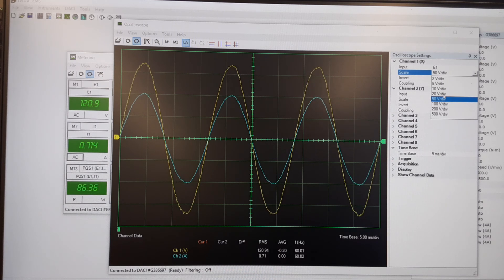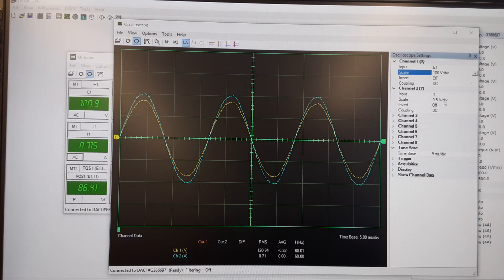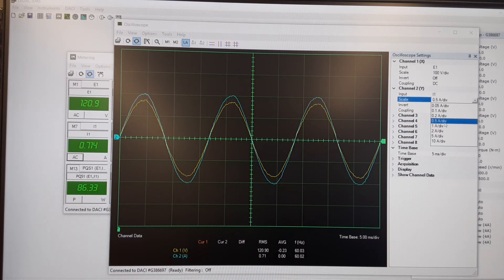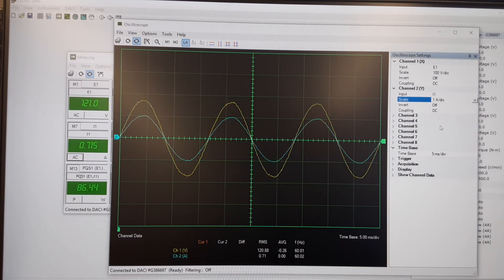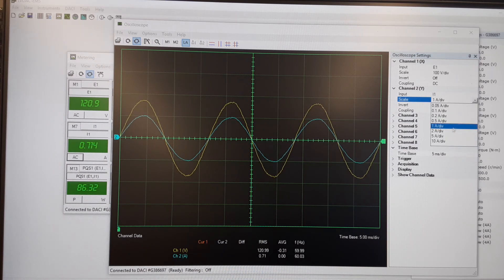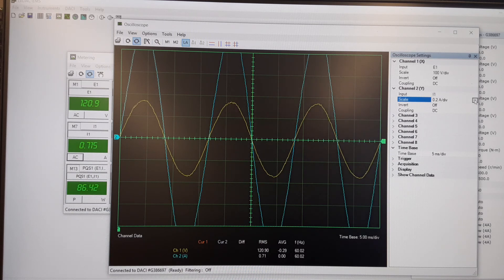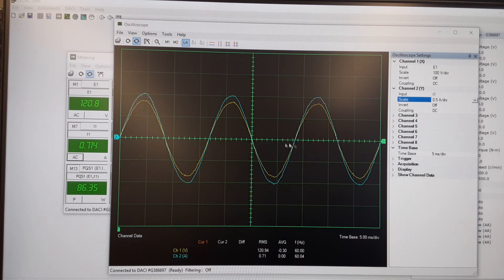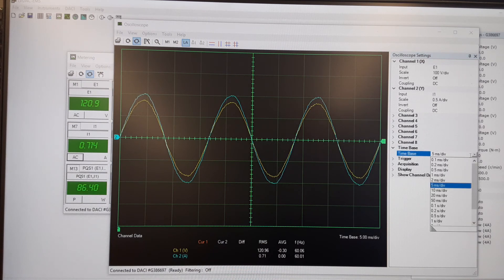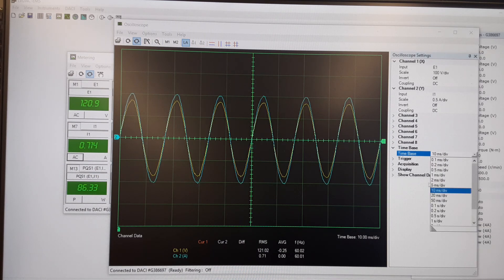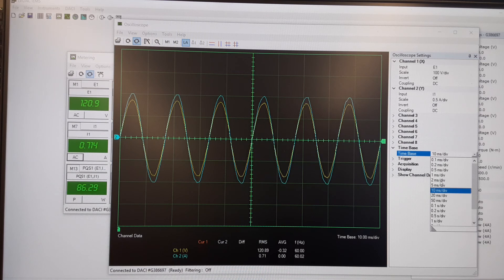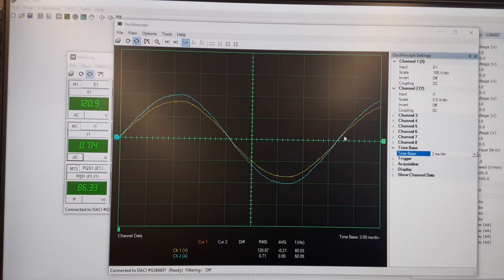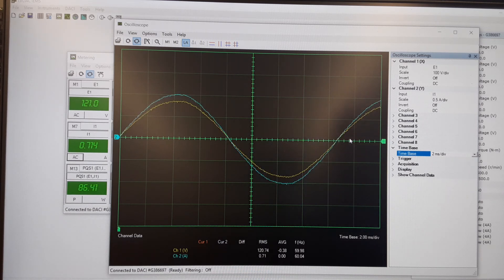So if I wanted to make it smaller, I can do 100 volts per division. If I wanted to make the current smaller, I could go to 1 amp per division. If I wanted to make the current bigger, I could go to 0.2 amps per division. But then that takes it off the screen. I can also adjust my time base here if I want to, to see more or less signals on my screen. So I can do 10 milliseconds per division and increase the number. Or I could do 2 milliseconds and decrease the number of sine waves on the screen.